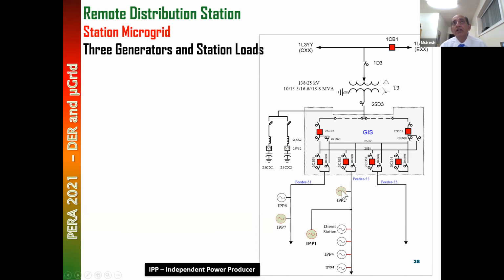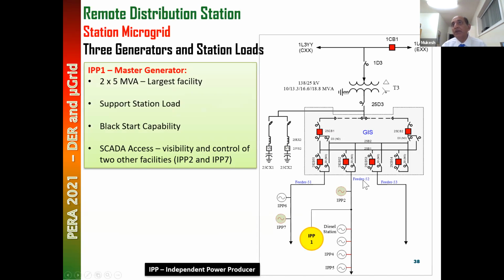So we selected IPP1, the largest one, as the master generator. It has a black start capability because if you have an unplanned outage, as I said, it is not a planned microgrid. If you have a fault here, everything trips. We need to start, and for that we need a black start capability. So this one has it. That means if the station goes black, we can pick up the load by black start and form a microgrid. This can support the entire station load. Therefore, we selected it. Plus, being the largest one and having a relationship with these two other plants, it had the ability to control them too.